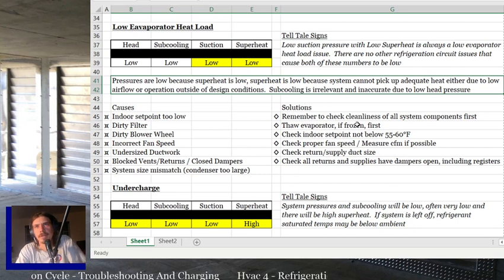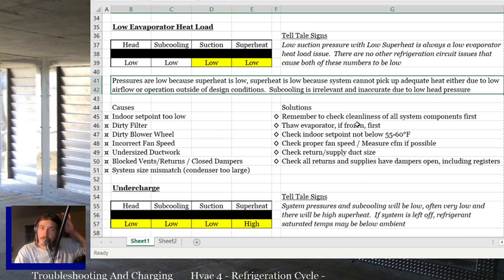So if you've got low evaporator heat load, what's going on is most people say low indoor airflow, because mostly when you see low evaporator heat load, it's going to be low airflow. But if you've got low outdoor temperatures and you don't have very good head pressure control and you're trying to maintain a pretty cool temperature inside, like in a data center or something like that, you could have low evaporator heat load and it be normal. If somebody turns the temperature down way too low on a thermostat, we really can't maintain temps below 55, 60 degrees, and even that's kind of pushing it with an AC system made to cool a house. That's low evaporator heat load. It's not really made to work in those temperatures unless you've got controls to help it do it.